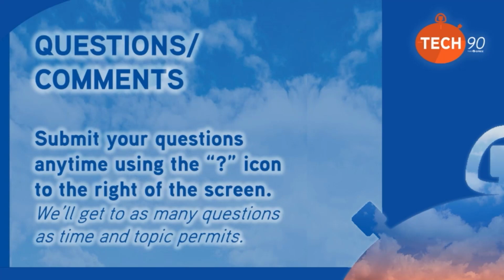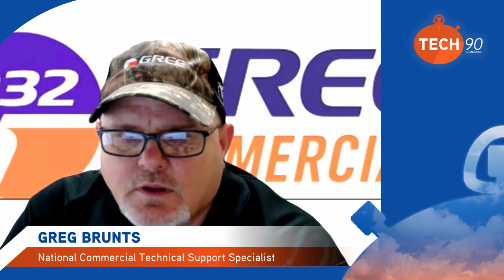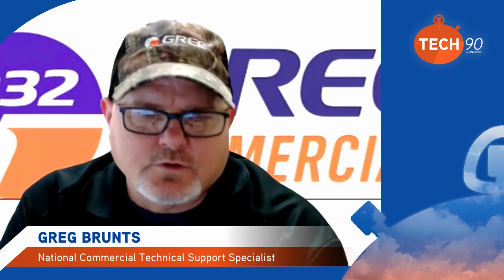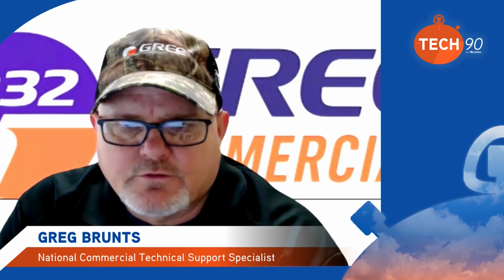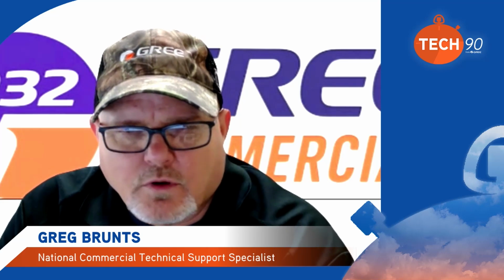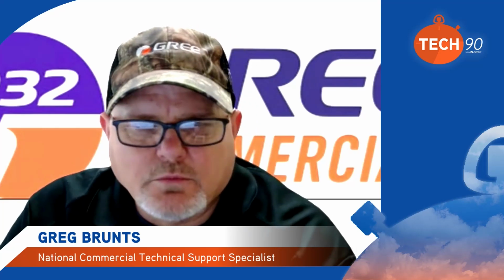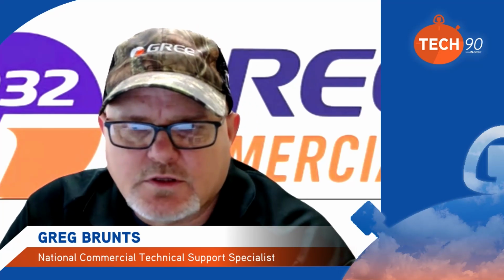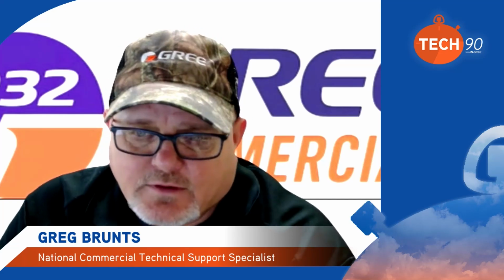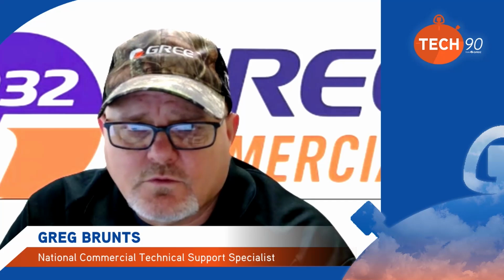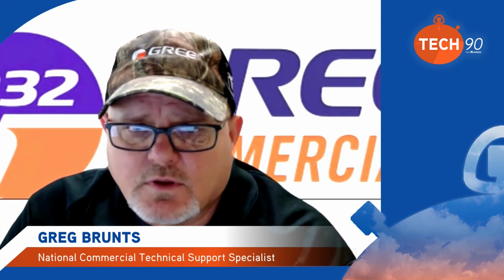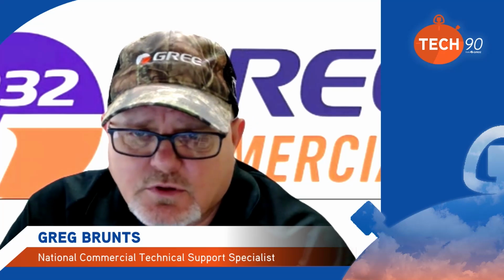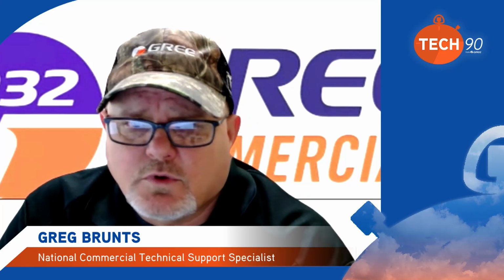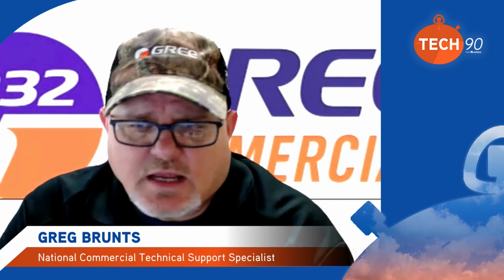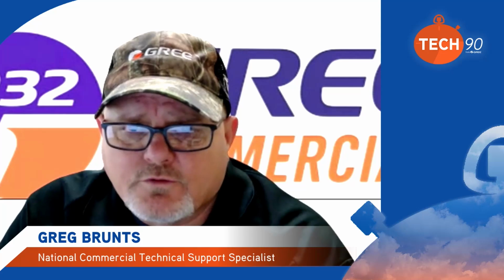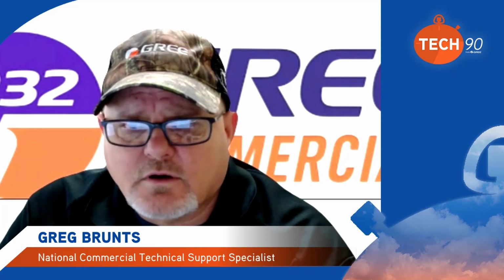All right, welcome back, everyone. Hope you enjoyed that video of showing you how the refrigerant flow goes on the MultiPRO system versus a multi-zone system, and understanding how they work, to understand more how you troubleshoot them, and then the service tool and the great information that service tool gives to you. Like I said before, and I've said multiple times, I think that service tool is worth every penny. It just makes troubleshooting that unit so much easier. Not only can you troubleshoot the unit, but you can actually drive the system from there. So whatever indoor unit or outdoor unit you're standing next to and you're hooked up to, you can drive the whole system from right there, and you can run all your diagnostics, try to figure out what's giving you the problem with that unit.